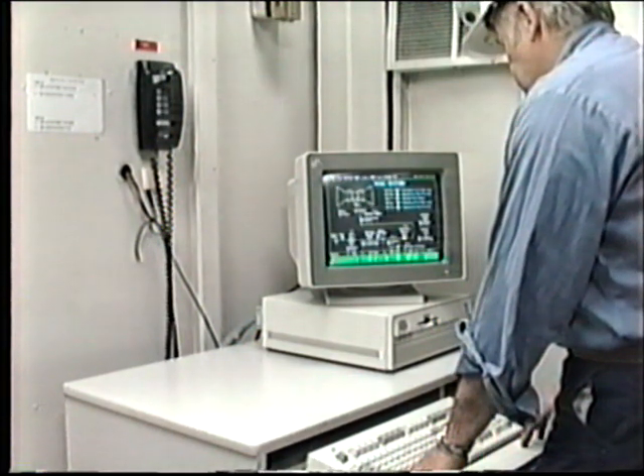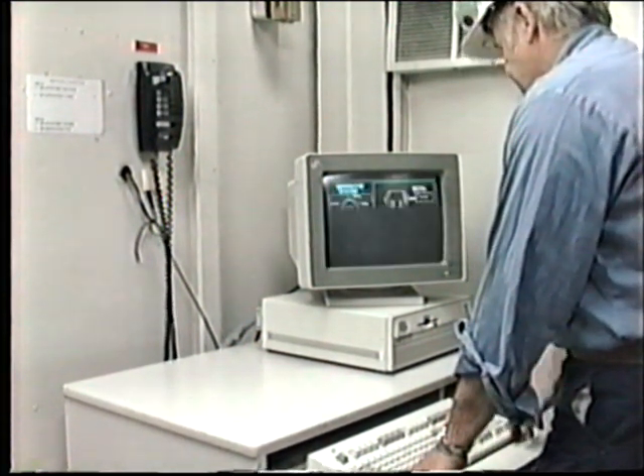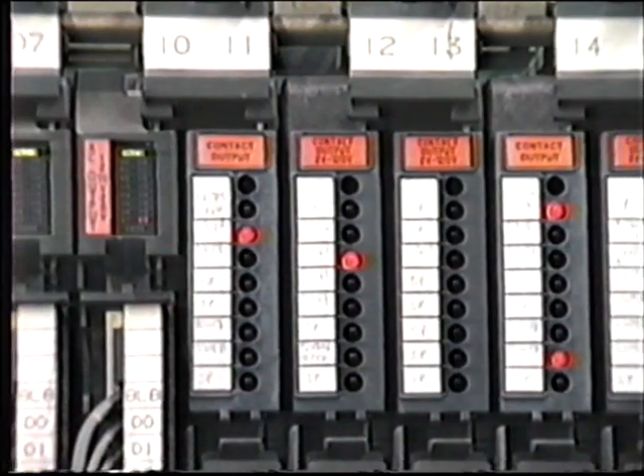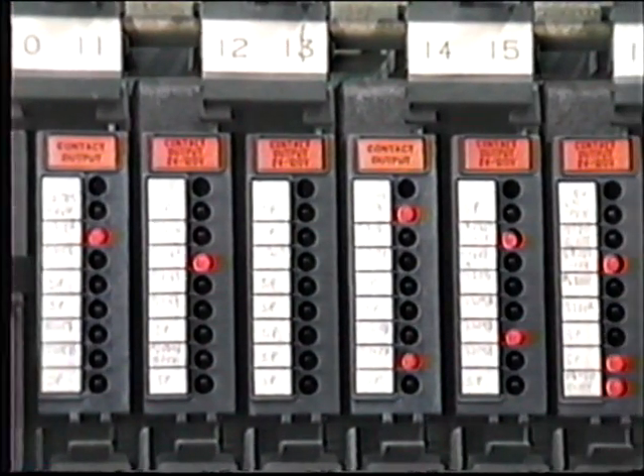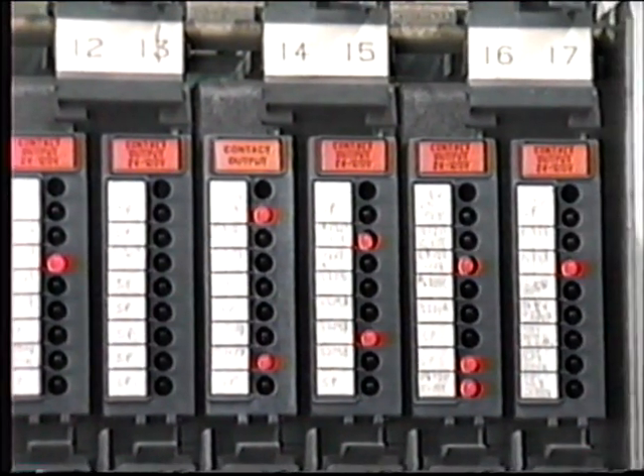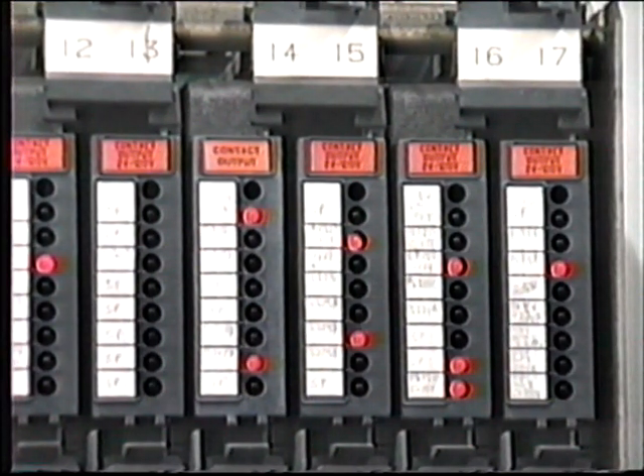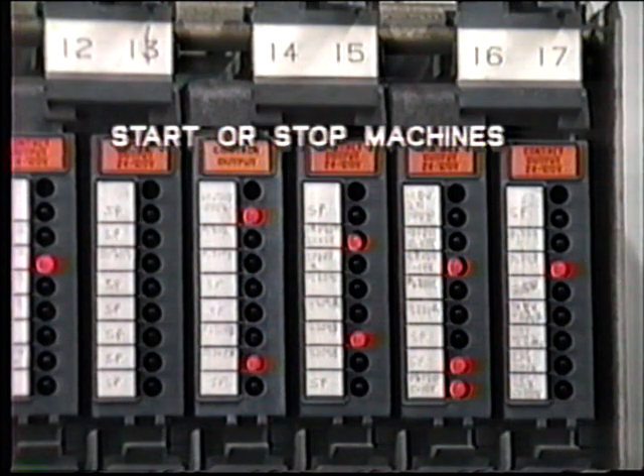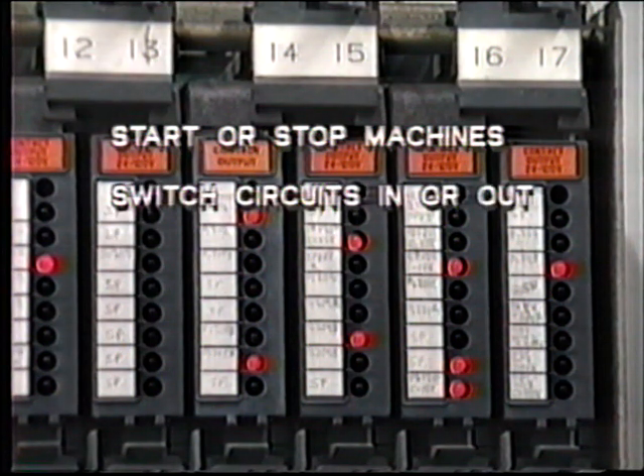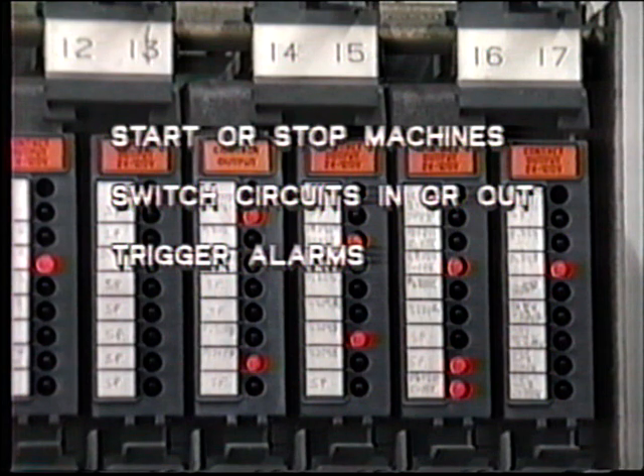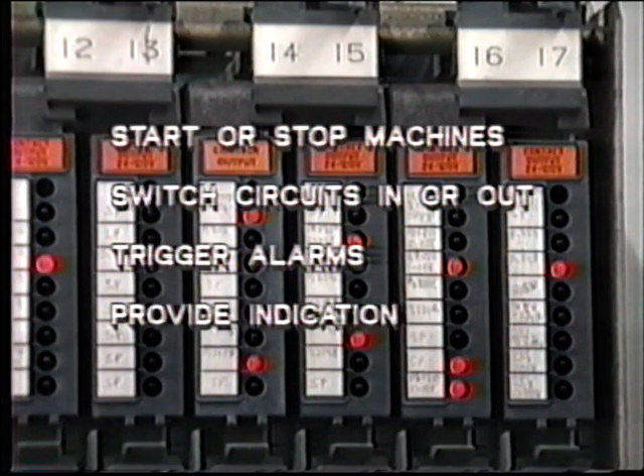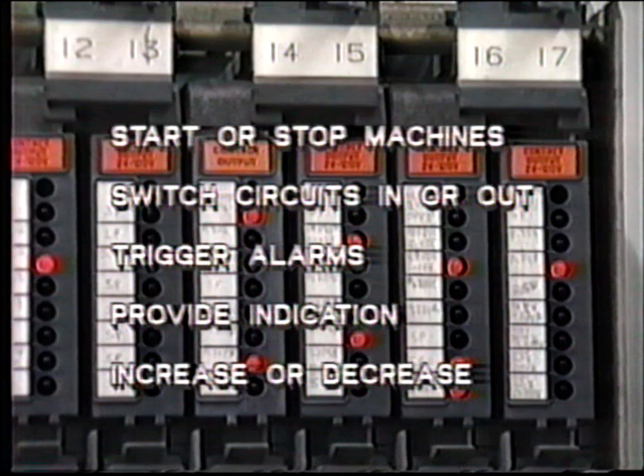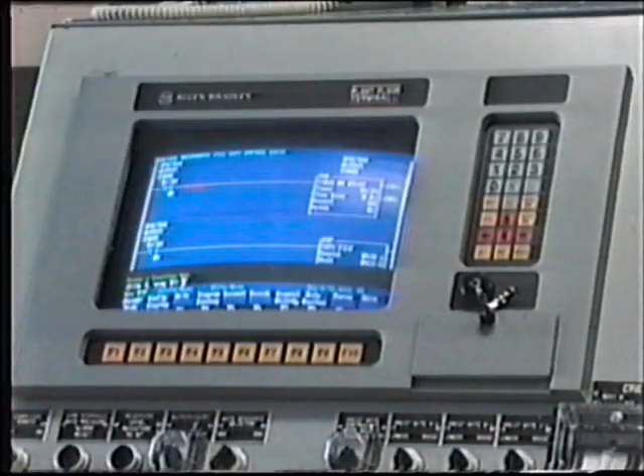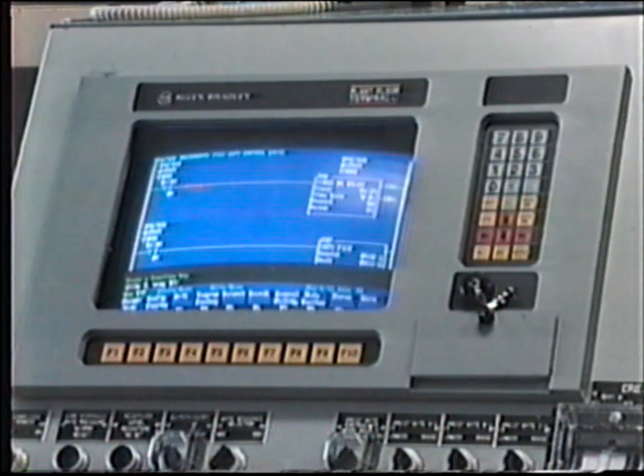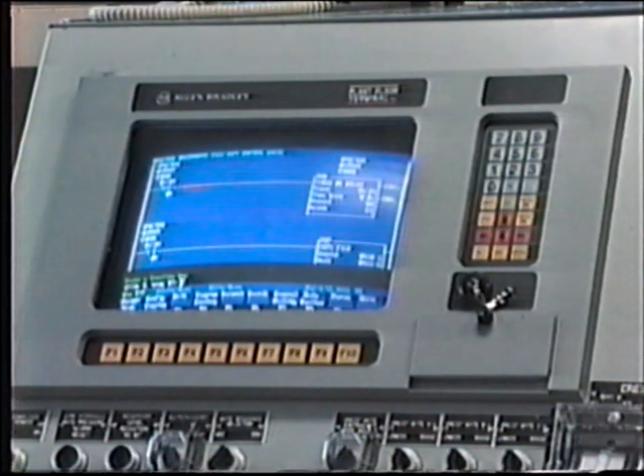Input signals give information as to the status of the process being controlled. Outputs from the logic circuits are usually in the form of an energized relay or transistor, which will initiate the desired action, for example, to start or stop machines, switch circuits in or out, trigger alarms, provide indication, increase or decrease speed. In many cases, the logic circuit includes such devices as timers, counters, and latching devices.